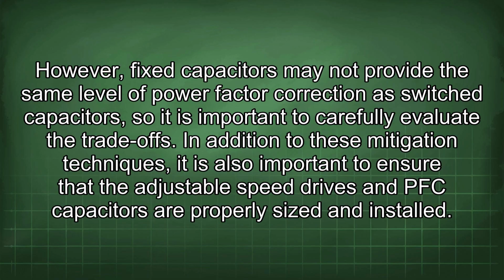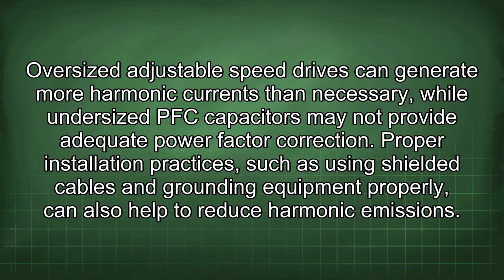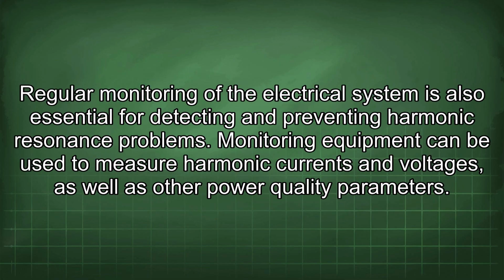In addition to these mitigation techniques, it is also important to ensure that the adjustable speed drives and PFC capacitors are properly sized and installed. Oversized adjustable speed drives can generate more harmonic currents than necessary, while undersized PFC capacitors may not provide adequate power factor correction. Proper installation practices, such as using shielded cables and grounding equipment properly, can also help to reduce harmonic emissions. Regular monitoring of the electrical system is also essential for detecting and preventing harmonic resonance problems.